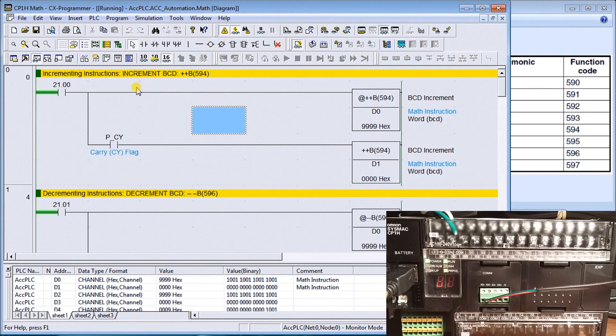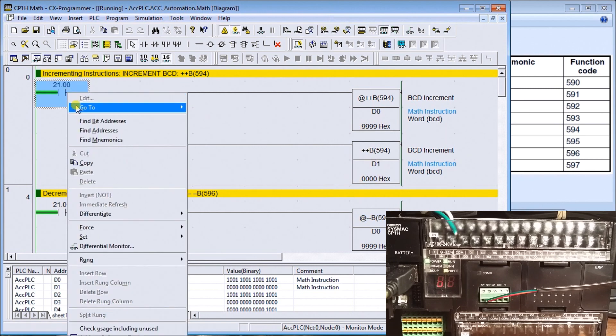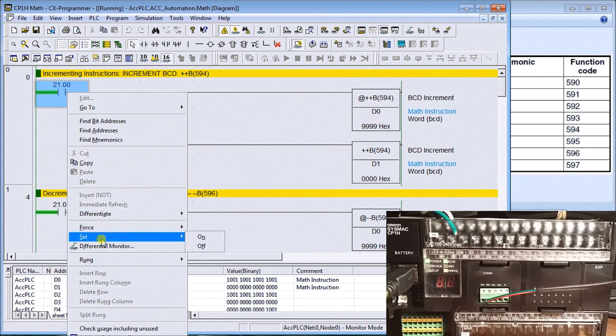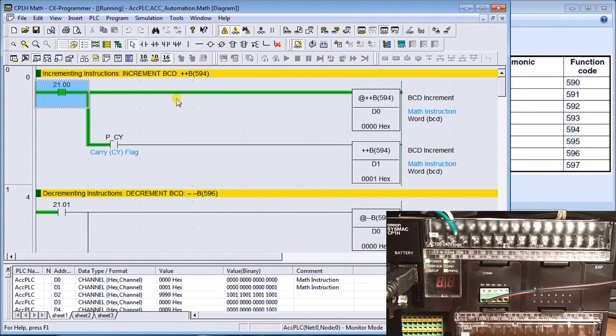The first example will be an increment BCD. We're going to turn on this bit, which will increment data memory zero. If the value is above 9999, it will turn on the carry flag, and the carry flag will then increment the next channel. We'll set that on, and sure enough, data memory zero turns to zero and data memory one goes to one.